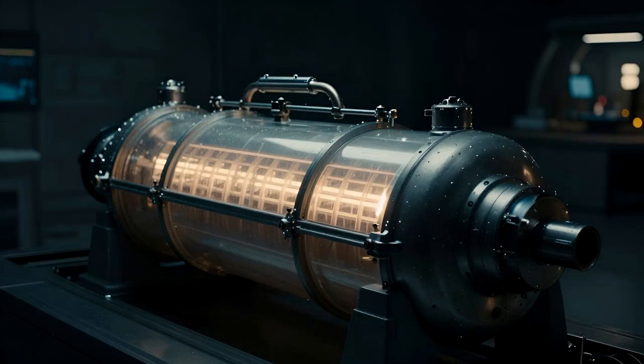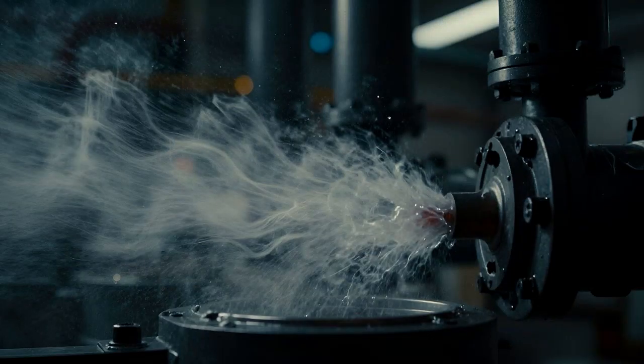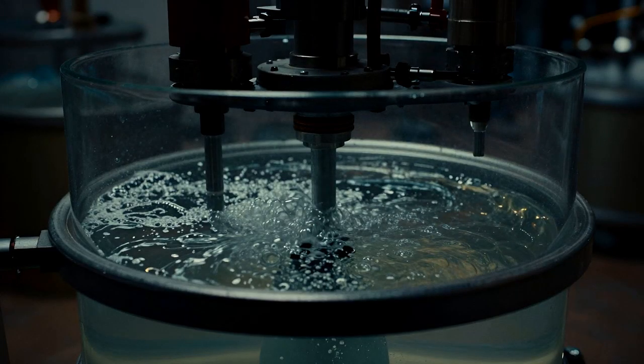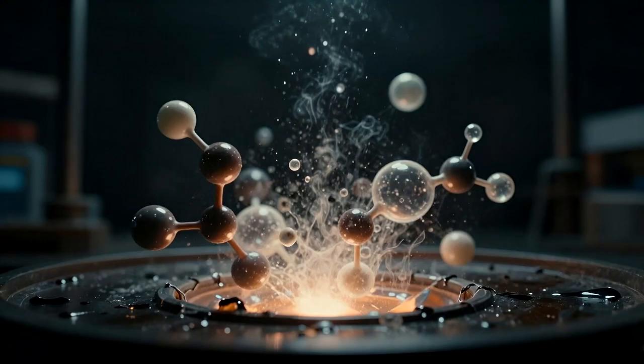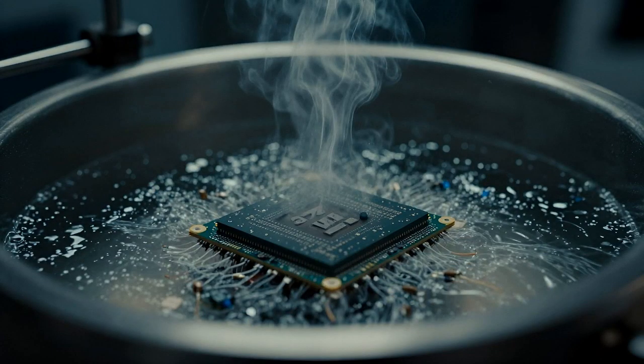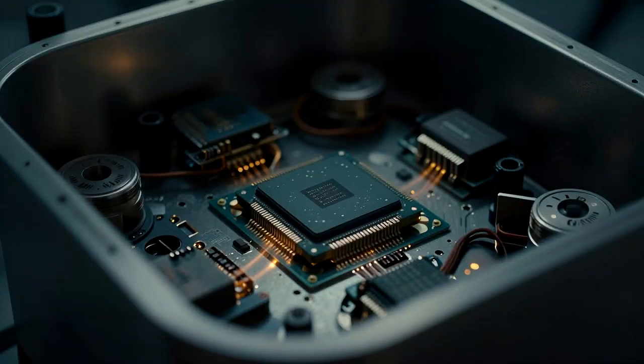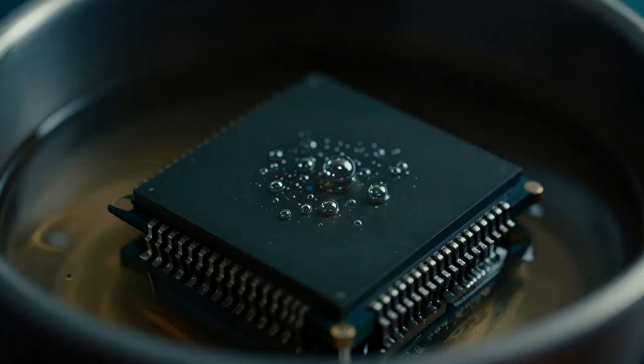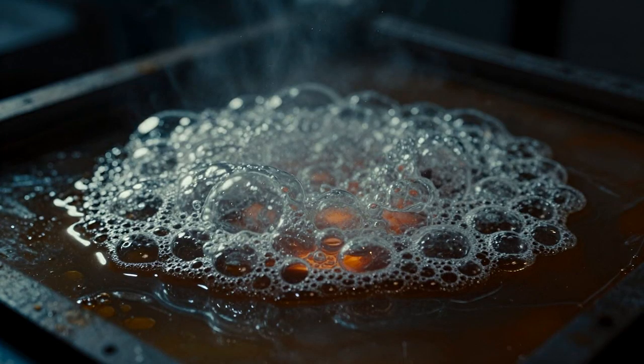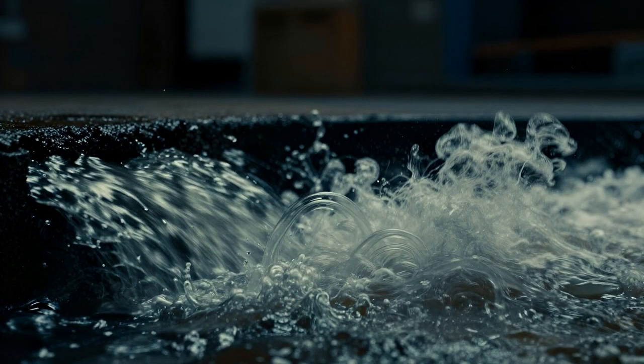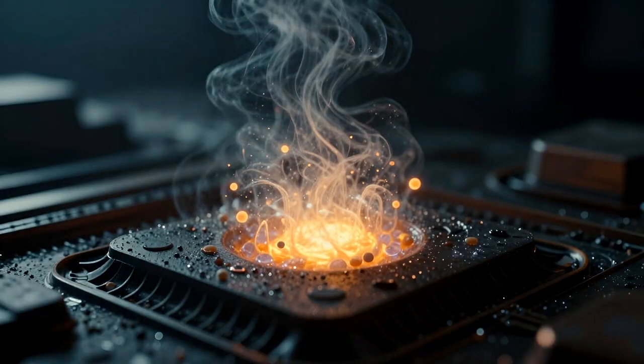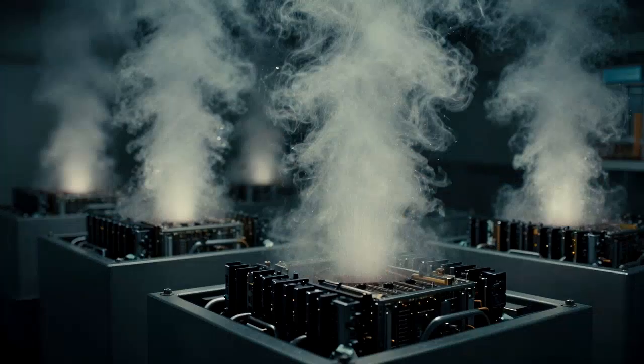This represents the absolute technological pinnacle of thermal management, leveraging the awesome, raw power of phase change physics. In these complex systems, the tank is filled with a highly specialized, engineered fluorinated fluid that has been chemically designed to possess an exceptionally low boiling point, often engineered to boil between 34 degrees Celsius and 56 degrees Celsius. When the powerful artificial intelligence chips engage, their surface temperatures quickly exceed the fluid's low boiling point. The fluid in direct contact with the hot silicon instantly boils, transitioning violently from a liquid to a vapor. This phase change, capitalizing on the latent heat of vaporization, absorbs massive amounts of thermal energy far more rapidly and efficiently than any circulating liquid ever could.